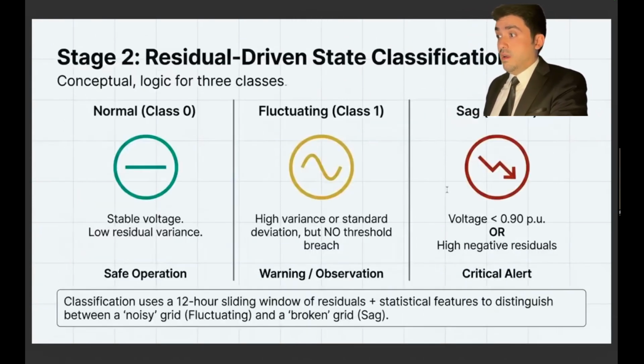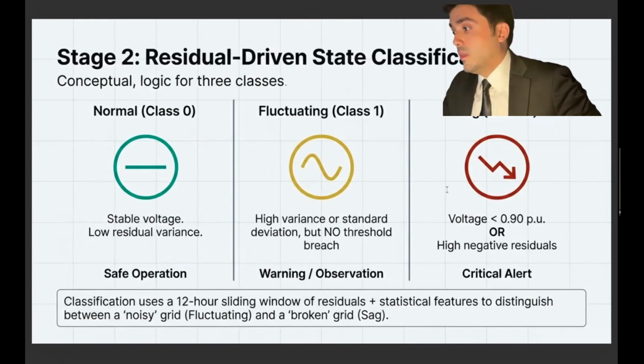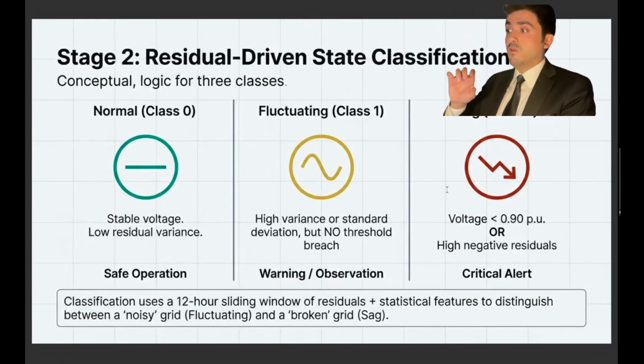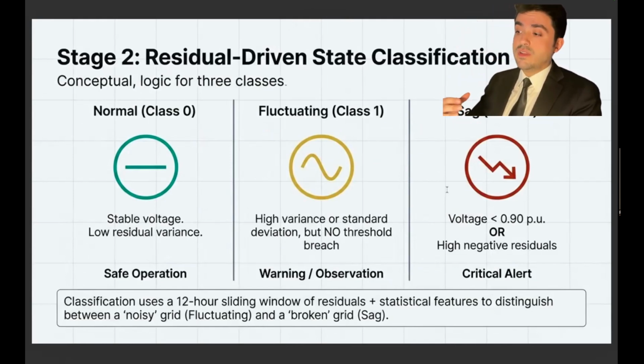Voltage states are classified using a 12-hour sliding window approach. Normal states exhibit stable voltage and low residual variance. Fluctuating states show increased variance without threshold violation. Sag states are characterized by voltage drops below 0.9 per unit or strong negative residuals, indicating critical conditions.